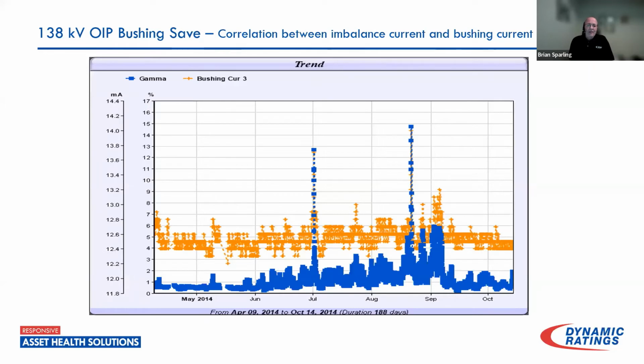So in this case, we're looking at a correlation between the imbalance current and the bushing current on phase 3 of that transformer. So it overlays nicely. It's telling you which bushing is having the problem, so you don't have to go out and begin hunting for it.